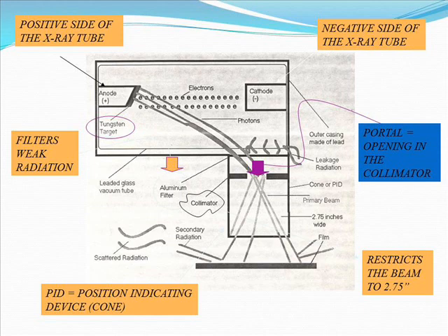So if you look at page 15, you can see in the bottom of the page, figure 215, you have a lead washer right there, and that lead washer goes in your cone and restricts the beam so that it only comes out of the very middle or center of that cone. If you look at the picture right above it, figure 214, you can see in the X-ray head itself the aluminum filter that's in the head itself, and then the black collimator that is in the end of the cone.